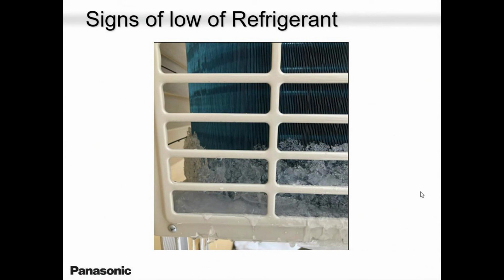Always be well equipped. Once you know you're well equipped, you will never be disappointed, guys. 32 years I'm in this trade. And I have seen a lot, and I'm still seeing day in, day out. Always remember, the temperature difference between in and out should be around 13 to 15 degrees Fahrenheit. Okay? After 10 to 15 minutes of operation, use your running amp. The last thing you want to do is hook up your gauges. Because I know when you hook up your gauges, you run away with a few ounces. No matter how sharp you are, you will run away with some ounces.